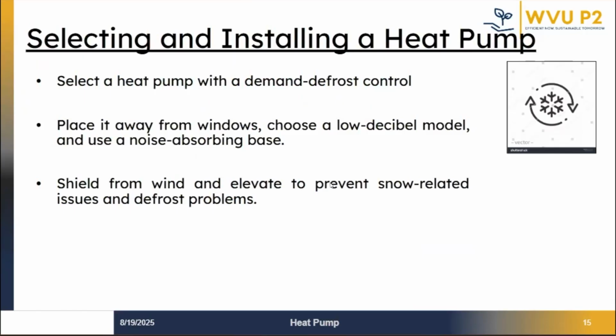Another is that fans and compressors always make noise. So we should locate the outdoor unit away from the windows and adjacent buildings and select a heat pump with a lower outdoor sound rating. We can also reduce noise by mounting the unit on a noise absorbing base. Also, the location of the outdoor unit may affect its efficiency. Outdoor units should be protected from high winds, which can cause defrosting problems, and may need to be elevated due to snow buildup.